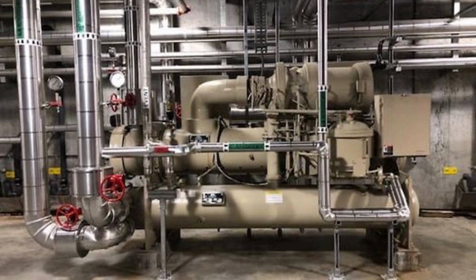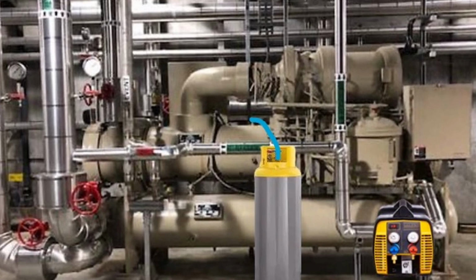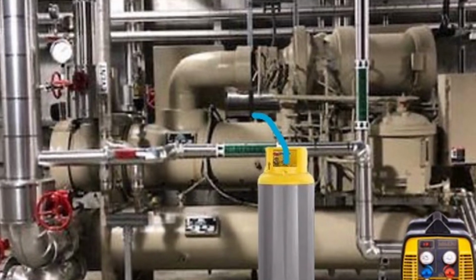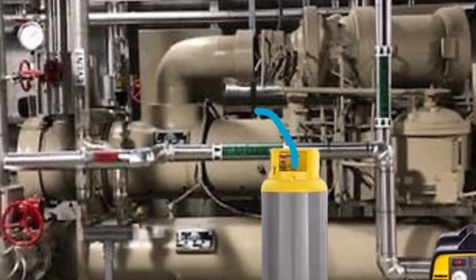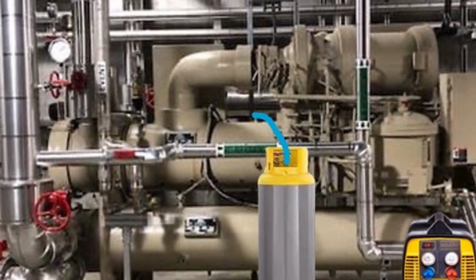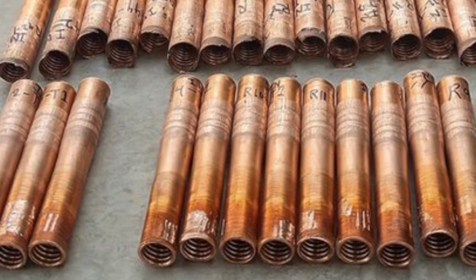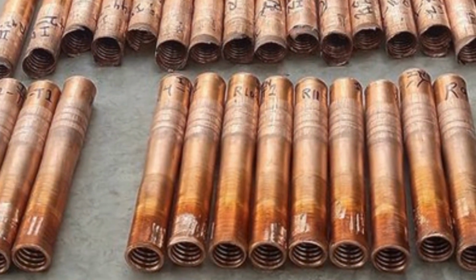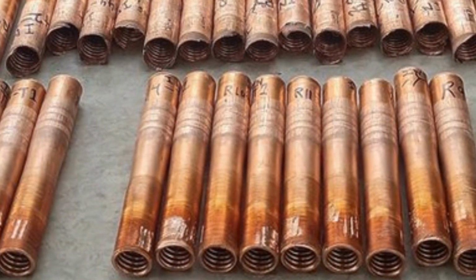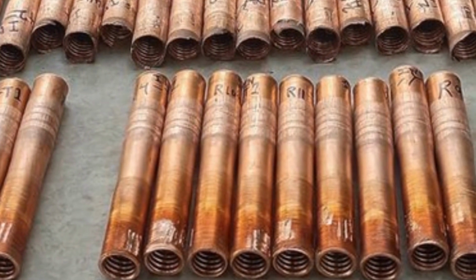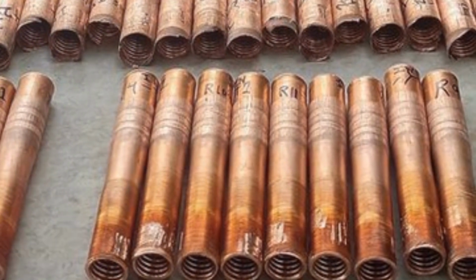When you're recharging the machine, you will add vapor to the system first, until you get the saturated refrigerant pressure above 40 degrees. If your hose starts to frost up, or the vessel starts to get cold, stop. Take a break and let everything warm up. It is extremely important that you keep the entire vessel above freezing to prevent your tubes bursting. Beginners and seasoned technicians alike have done this. I've been lucky enough to hear the horror stories from other technicians before I made the mistake myself.